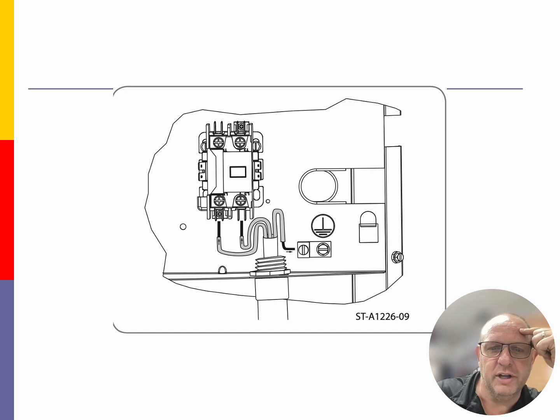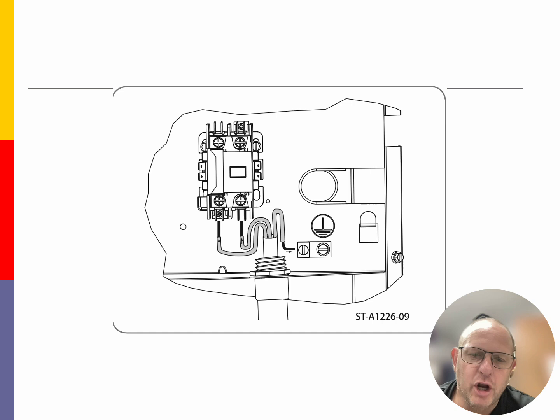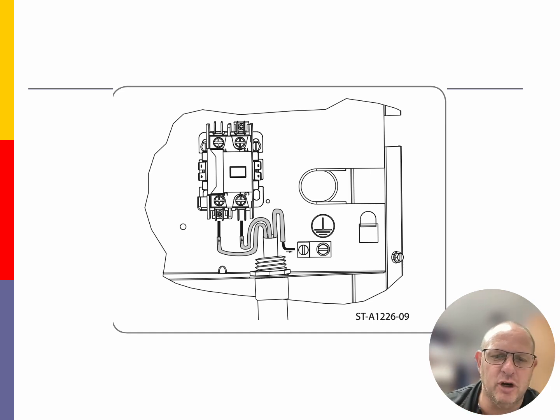So we're continuing our conversation on the electrical hookup of the outdoor unit and the indoor unit. What we're looking at here is when you bring in power to the outdoor unit, you're going to do so through a type of liquid tight connector, because the condensing unit is sitting on the outside of the house. And then after I've brought it into the electrical compartment of the air conditioner, I'm going to land that electrical right on the contactor on the L1 and L2 terminals. Now, these should be labeled on the contactor, L1 on this side, L2 on this side, or something very similar. I could have flip-flopped the L1 and the L2 if I needed to. And then on the top up here would be a T1 and then a T2 on the other side.